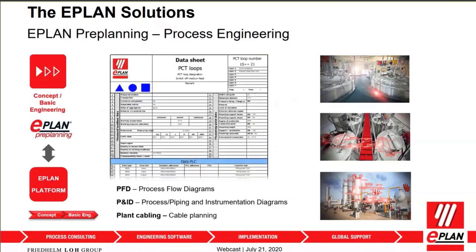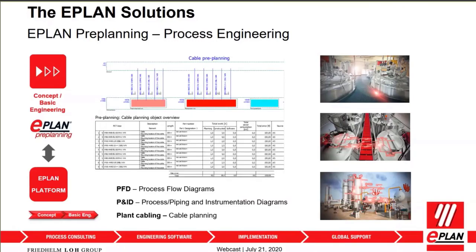You can generate documentation directly from the system, such as data sheets. If you need to order temperature, pressure, or flow sensors from a manufacturer and need to identify parameters — minimum values, maximum values, environmental considerations — all of that can be generated into a data sheet and sent to the manufacturer automatically. For cable pre-planning, you can pre-plan how many sensors are in one area of your plant and where your DCS system is, so you can plan cable routing. These topics, done early in engineering, can all be captured in ePlan preplanning.